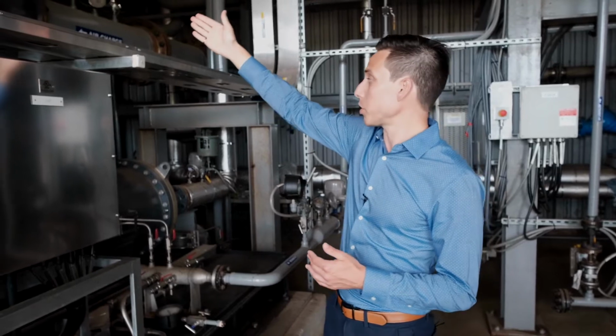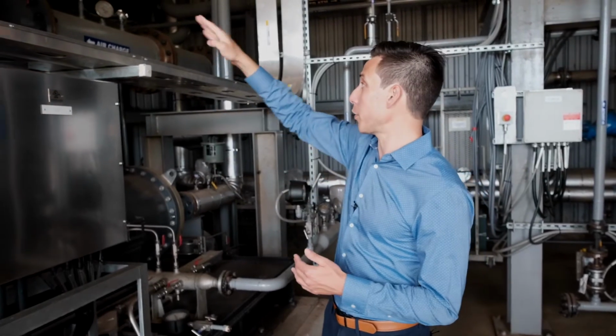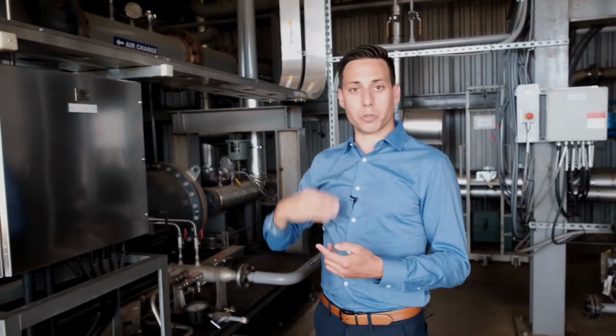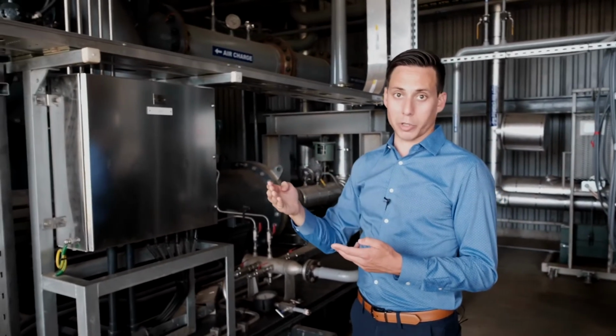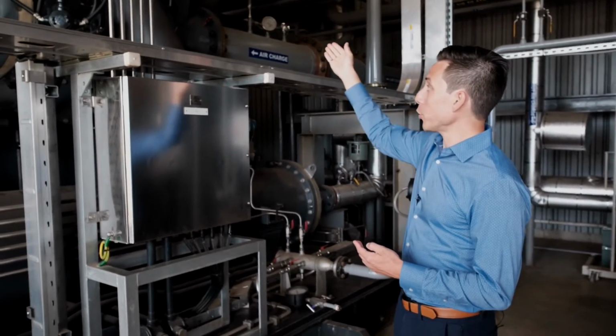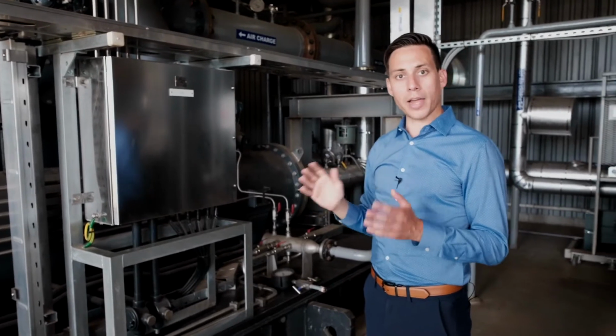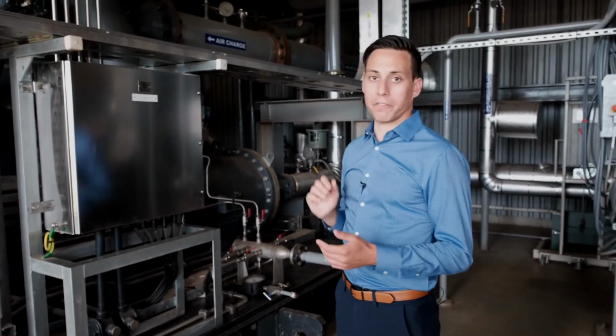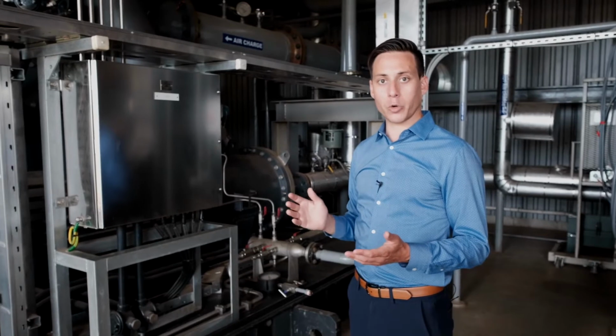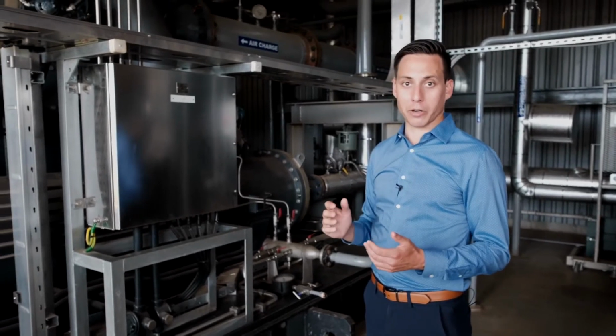The air comes from the filter that we saw earlier, first into this first stage of the compressor, where it sequentially goes into the second and third stage. At each stage, its pressure is increased as well as its temperature. By the time it exits the third stage of the compressor, it's about 9 bar in pressure and 250 degrees Celsius. 250 degrees is about broiling temperature of your standard kitchen oven.